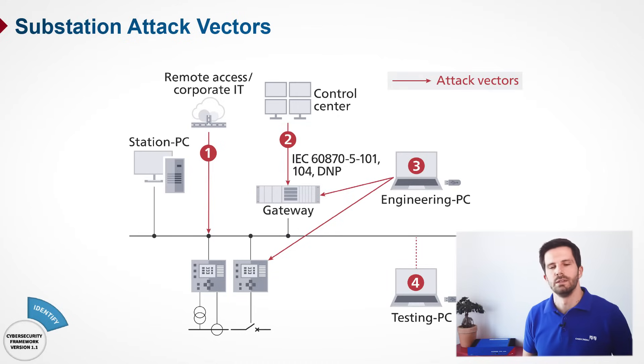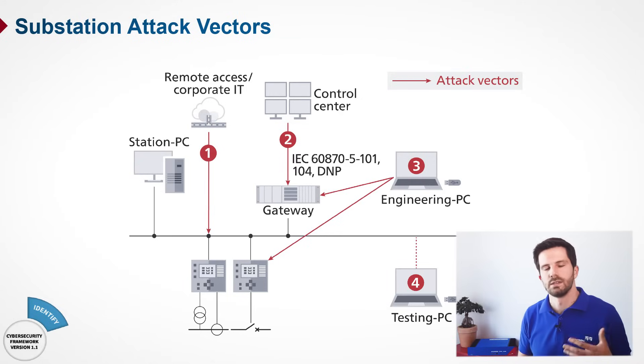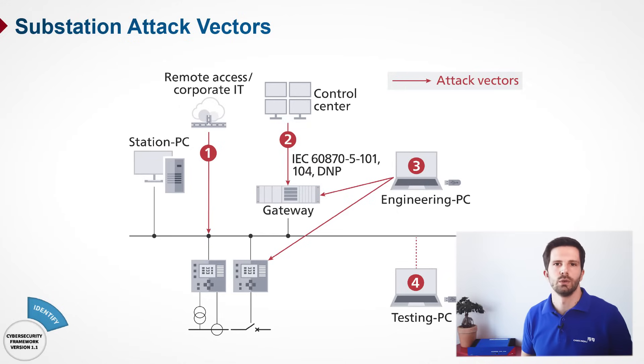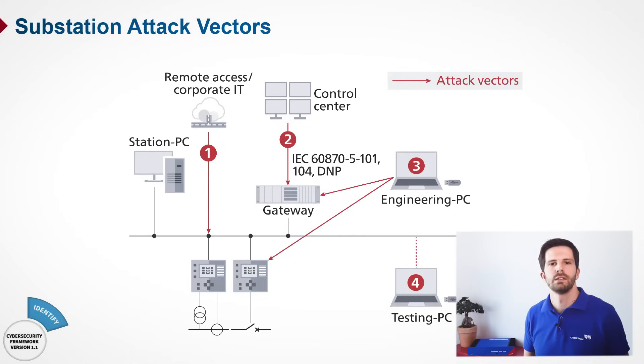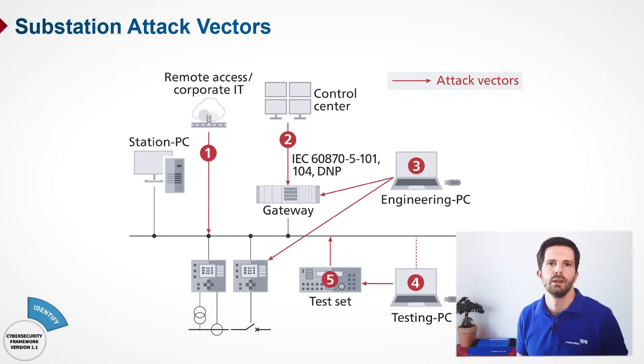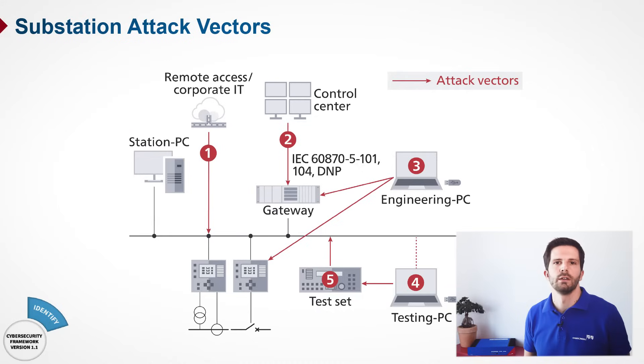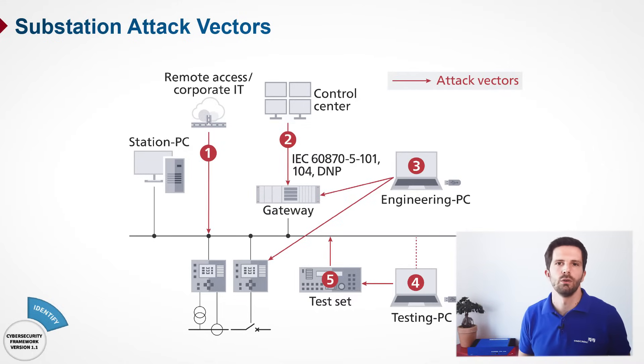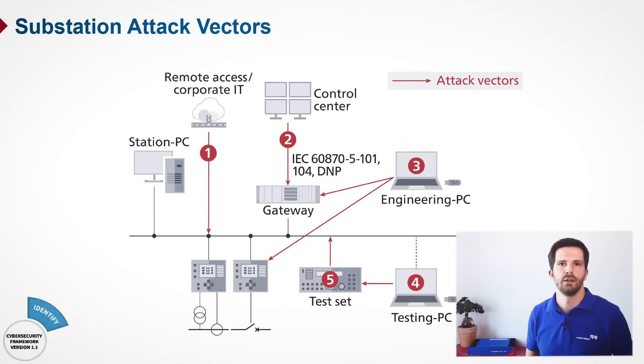Something which is often forgotten is that Stuxnet-style cyber attacks using engineering laptops directly connected to devices in the substations are also feasible. This happened ten years ago in the Stuxnet cyber attack, but it can happen again in substations as well. Another topic is testing PCs, especially for SCADA testing and signal testing involving IEC 61850 or without — typically Windows software is plugged into the substation or SCADA network, which also poses an attack vector. The testing devices used to test protection or communication functions are also an attack vector, and as a test set vendor we are investing heavily to make this attack vector unattractive.